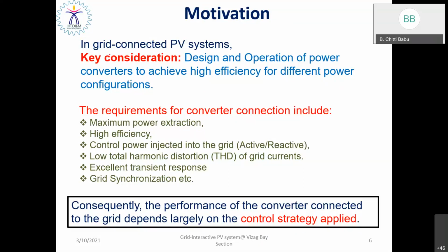In such a grid connected or grid integrated solar PV system, the key consideration is the design and operation of the power converters to achieve high efficiency for different power configurations. You know, designing active power converters to integrate a solar PV system with the utility grid is a great challenge with high efficiency, because the input energy is variable, and hence the output power of the PV cell is also variable, right? So it cannot be directly connected. Even if you have a very dedicated high performance power converter, still the grid integration is not possible 100%, right?